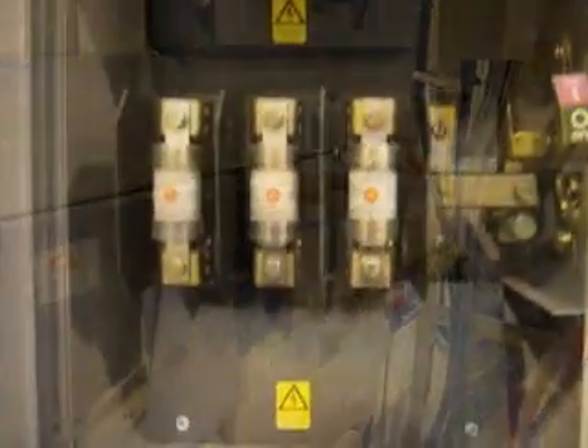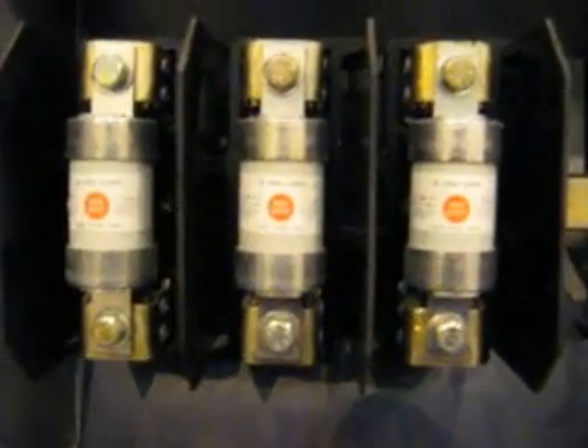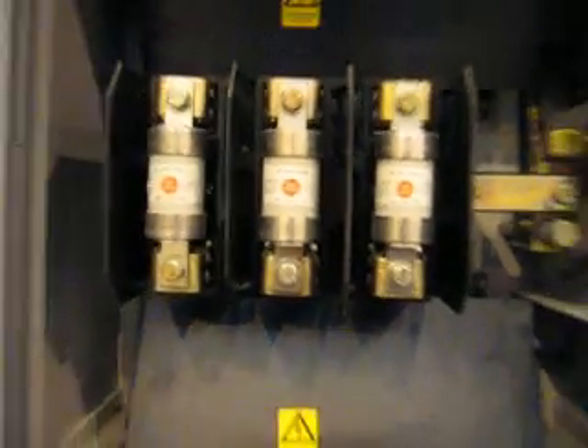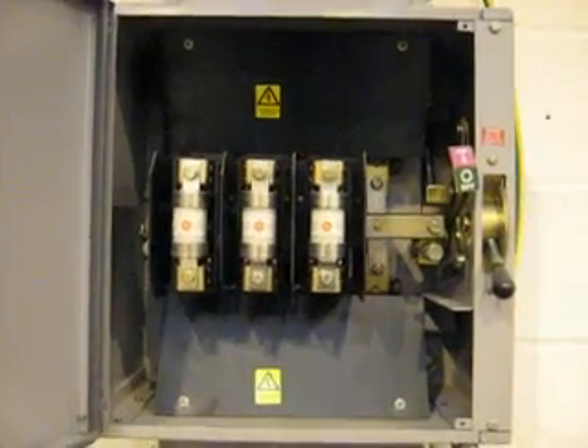Busbars here are the feed to the busbar chamber, and that confirms that this is in fact the main switch. That connects via that trunking onto the service. These fuses will have to come out when the switch is closed, and if it were switched on, it would be switching onto a short circuit. They are 250 amp HBC fuses, BS88 type gG. This fuse switch is serving no purpose and it should be removed.